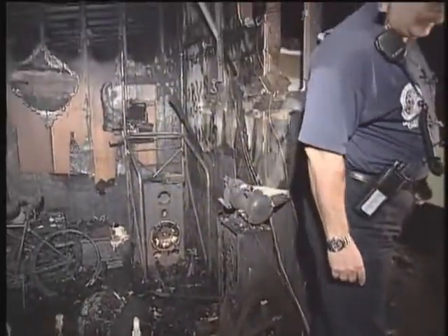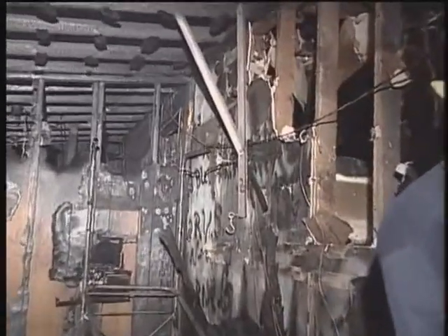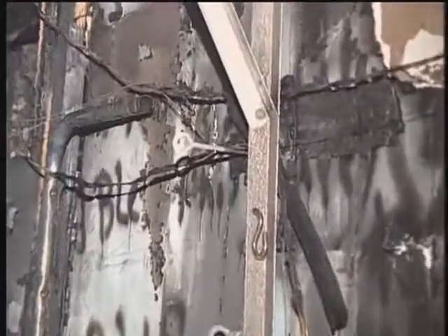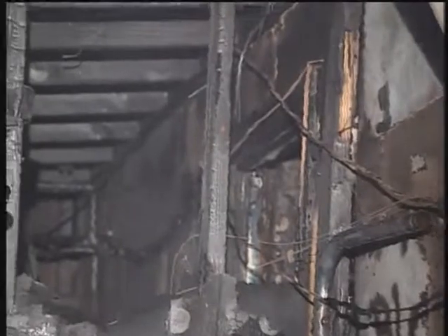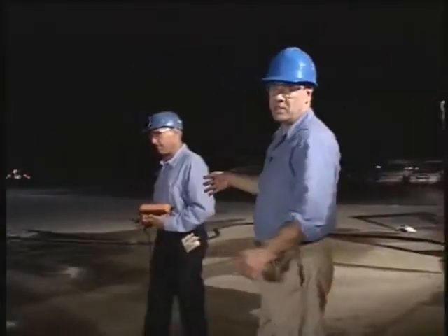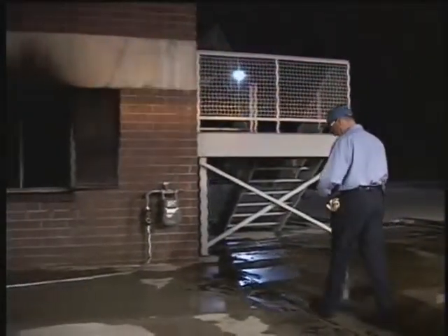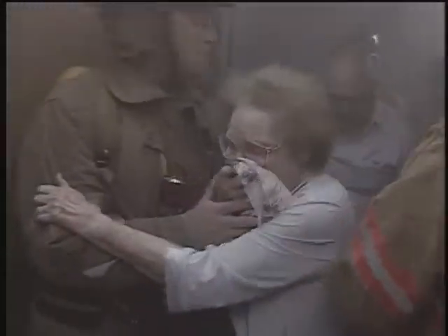Keep in mind and stay alert to the dangers of gas migration. What's not burning, but leaking may be traveling through ducts, such as wall cavities, ceilings, or excavations along the property. When is the area out of danger? When CGI testing shows no traces of natural gas in the air, and the environment is said to be zeroed out. If there is any doubt, evacuate.